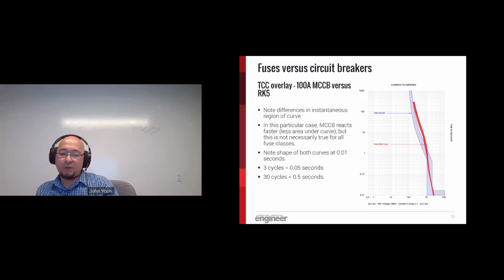So we talked about both fuses and circuit breakers. Let's directly compare the operating characteristics of the two. Of course, there's an incredible variety of fuses and circuit breakers, each with its own specific time current curves. However, to illustrate a point, let's look at generic fuse and circuit breaker time current curves. This picture is a direct overlay of both of these. The fuse is red, the circuit breaker is blue. When they are overlaid, the difference is quite pronounced.